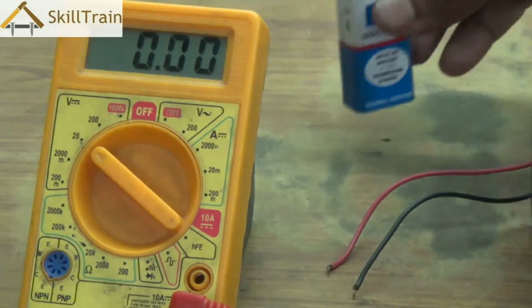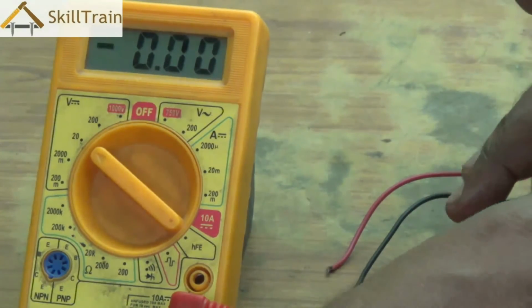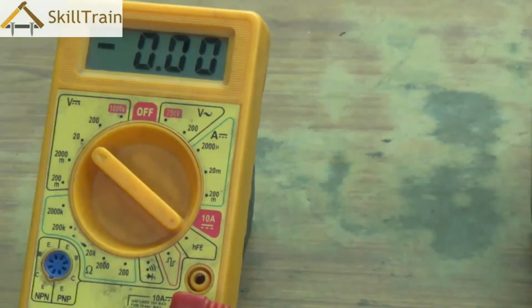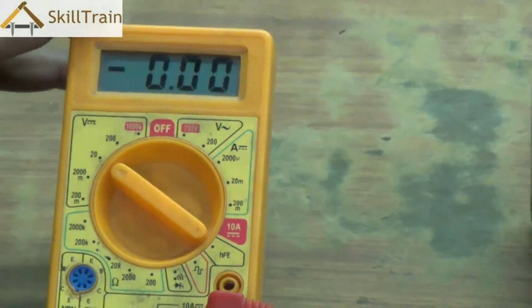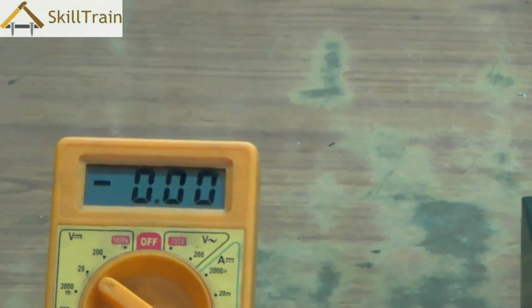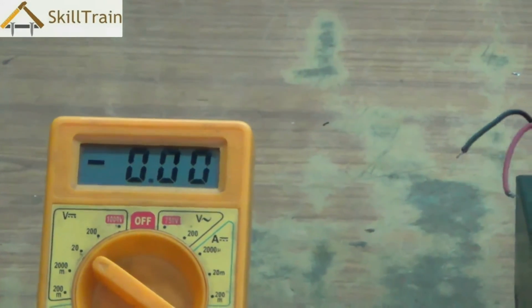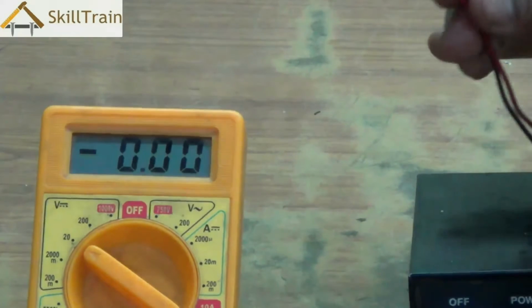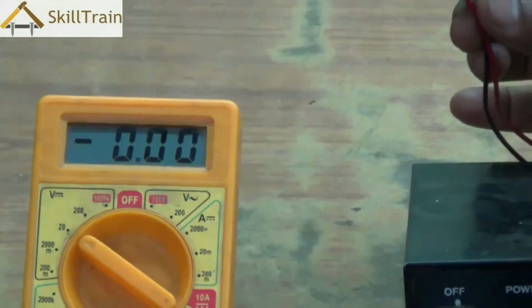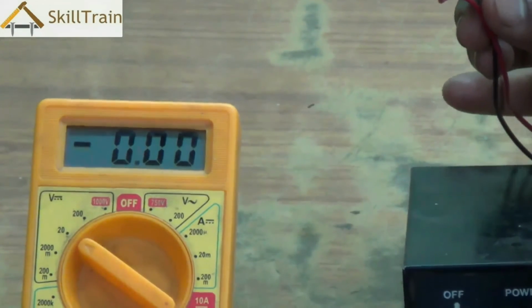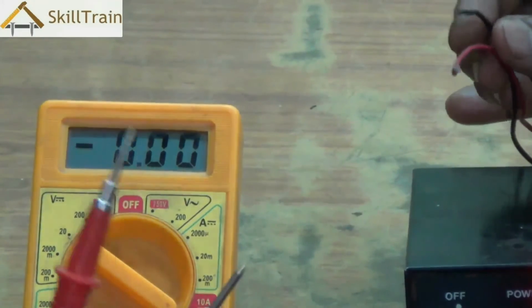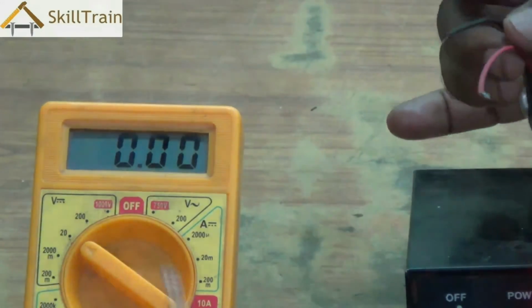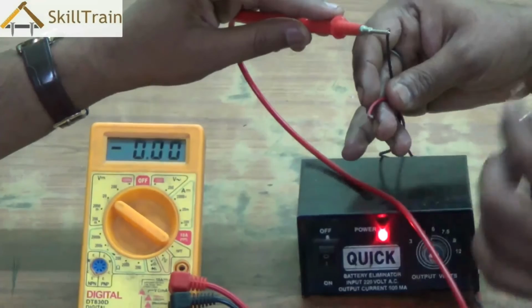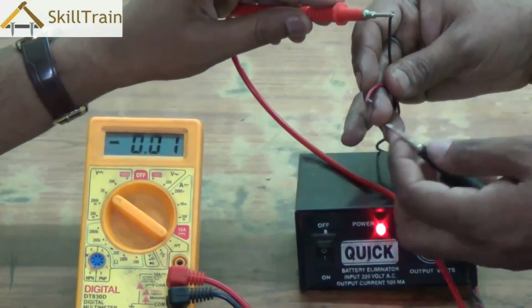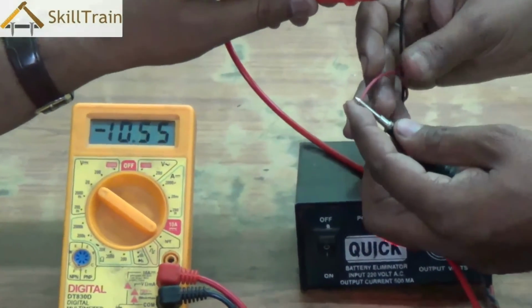Now you can do the same thing with the transformer in front of us. We are going to place the probes on the output leads of the transformer to see which is the positive and negative side. Let's connect the probes to these two points without any particular reference to positive or negative, and see what happens. We've switched on the transformer now and are placing the probes on the two leads.